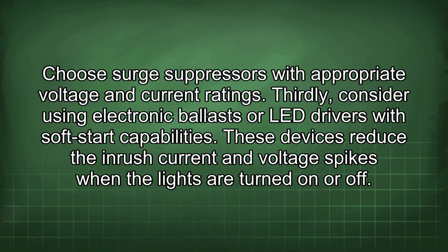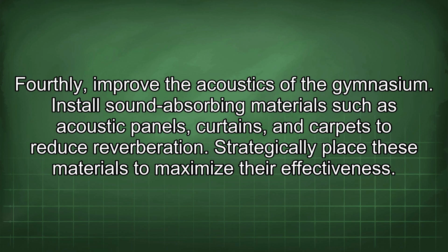Choose surge suppressors with appropriate voltage and current ratings. Thirdly, consider using electronic ballast or LED drivers with soft start capabilities. These devices reduce the inrush current and voltage spikes when the lights are turned on or off. Fourthly, improve the acoustics of the gymnasium. Install sound-absorbing materials such as acoustic panels, curtains, and carpets to reduce reverberation. Strategically place these materials to maximize their effectiveness.